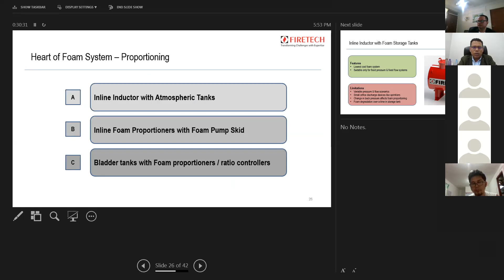So the features of this system: it is the lowest cost foam system, and it is suitable only for fixed pressure and fixed flow systems. Limitations: it cannot be used for variable pressure and variable flow scenarios. So for example, if from the same foam system you are trying to protect, say, three different zones, then this system is not suitable for that. Small orifice discharge devices like sprinklers cannot be used because the inductor is very sensitive to any blockages in the downstream piping or the discharge devices. A change in back pressure affects foam proportioning, and foam degradation happens over a period of time in the foam storage tank, because the tank is atmospheric, so it's open to air, and there are chances of the foam deteriorating over time.